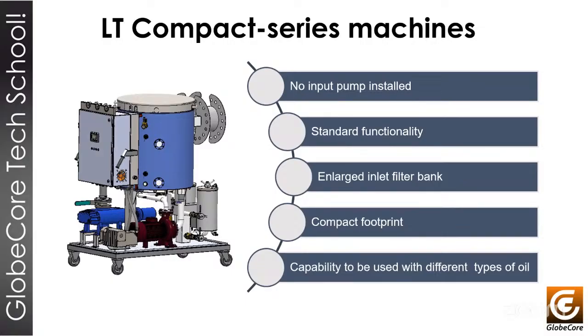Similar to the standard series, the machines feature no input pump installed. This machine doesn't have an input pump like the other machine. The vacuum pump will be responsible for the suction of the oil from the transformer, or from the tanks, or from the different storage places where you have the oil to be processed. You will use the vacuum pump in the machine for the ingress of the oil into the machine.